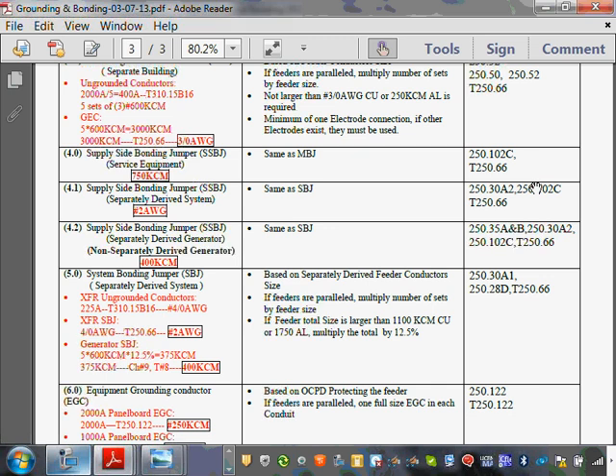Here's my transformer. You size your conductors first, and then from your conductors, you size the system bonding jumper, exactly like the grounding electrode conductor. Except if you go higher than 1100 kcmil, or God forbid you're using aluminum, 1750, then you start taking 12.5%. It's sized exactly as the main bonding jumper. System bonding jumper and main bonding jumper are identical in terms of sizing.